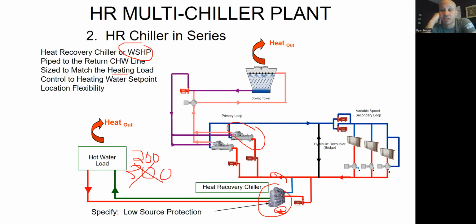It's just the heat pumps that are running. And then that water loop is just circulating heat between zones that want it and don't want it. And you still would have a cooling tower or boiler in the building, because if it didn't line up, like, oh, I took this much heat out of the loop, I only put that much on, the boiler's got to kick on and temper the water back up to something reasonable, or a cooling tower has to trim it off.